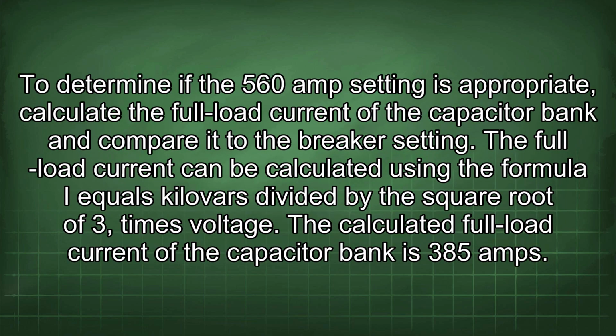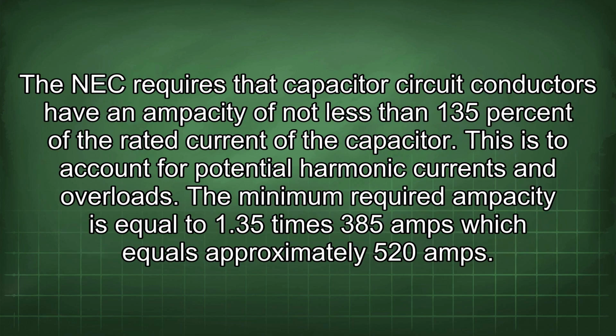To determine if the 560 amp setting is appropriate, calculate the full load current of the capacitor bank and compare it to the breaker setting. The full load current can be calculated using the formula I equals kiloVars divided by the square root of 3 times voltage. The calculated full load current of the capacitor bank is 385 amps. The NEC requires that capacitor circuit conductors have an ampacity of not less than 135% of the rated current of the capacitor. This is to account for potential harmonic currents and overloads. The minimum required ampacity is equal to 1.35 times 385 amps, which equals approximately 520 amps.